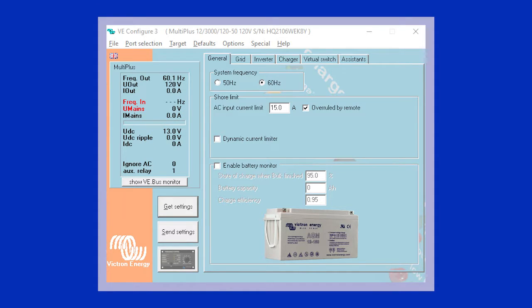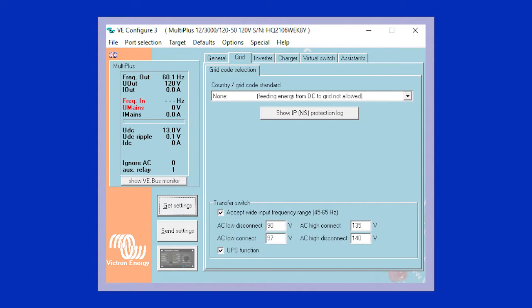But you do wanna check the box that says overruled by remote, because we're gonna have this connected to our Cerbo GX and display, and when I click this box, that means I'll be able to change the current limit on my device and not have to go in and do this. Obviously with the computer would be quite a pain every time. We're just going to go through the settings here. Grid, so we're not feeding any power back to the grid, so you can leave that as is. Transfer switch, I don't make any changes there.